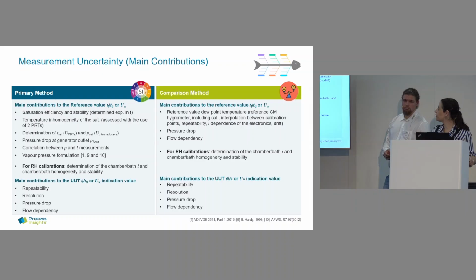And to finish, just to give you an overview of the main contributions for the primary and comparison methods. In the case of the primary, for the reference, the main contributions are the saturation efficiency and stability of our saturator, the temperature inhomogeneity of the saturator, determination of the temperature and the pressure, of course, the pressure drop, the correlation between pressure and temperature measurements, and also the uncertainty coming from the formula.